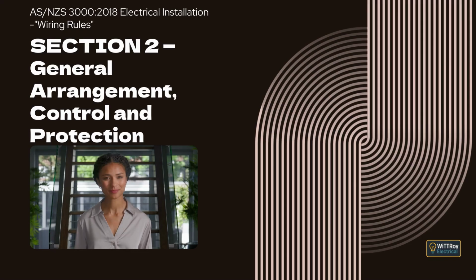Clause 2.10.2.4 explains identification of the main switchboard. The main switchboard must also be permanently marked with the words "main switchboard." The label must be clear, easy to read, and made of durable material. If the room or enclosure itself is the main switchboard room, that room must also be clearly marked, unless the installation is a small domestic one where the location is obvious.